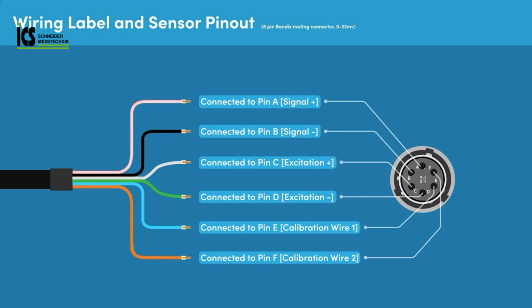The red wire is connected to pin A and is signal positive. The black wire is connected to pin B and is signal negative. The white wire is connected to pin C and is excitation positive. The green wire is connected to pin D and is excitation negative. The blue wire is connected to pin E and is calibration wire 1. And the orange wire is connected to pin F and is calibration wire 2.